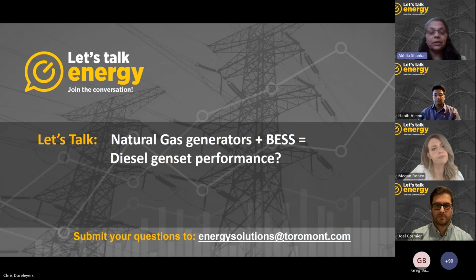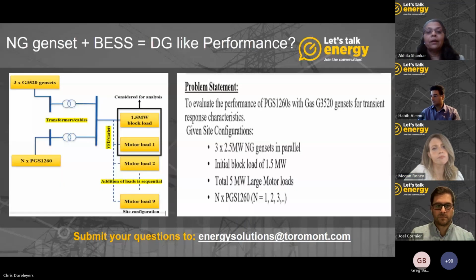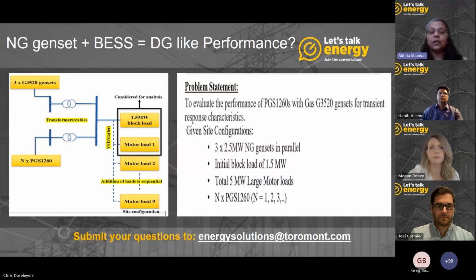Yes, if we can go to the next slide, please. Okay, in this case study, Caterpillar did the sizing and the stability calculations to see how many 1260 kilowatt rated battery energy storage systems are required to operate with three 2.5 megawatt standby rated natural gas gensets to achieve the specified transient performance, the diesel-like transient performance, for the given site-specific loading scenario.